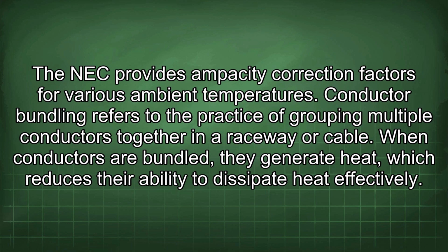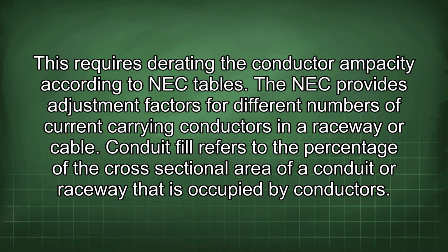Conductor bundling refers to the practice of grouping multiple conductors together in a raceway or cable. When conductors are bundled, they generate heat, which reduces their ability to dissipate heat effectively. This requires derating the conductor ampacity according to NEC tables. The NEC provides adjustment factors for different numbers of current-carrying conductors in a raceway or cable.